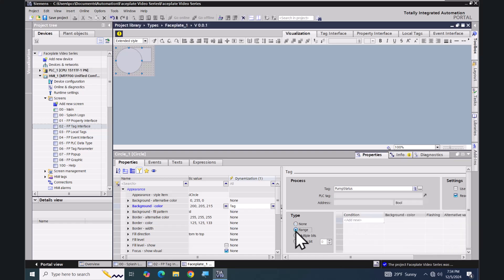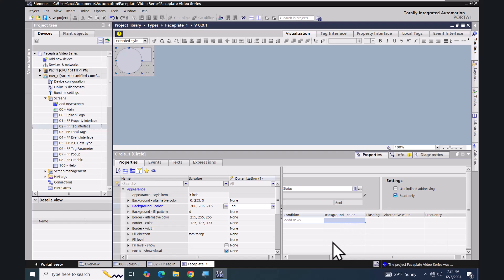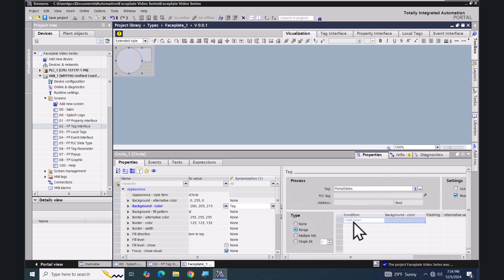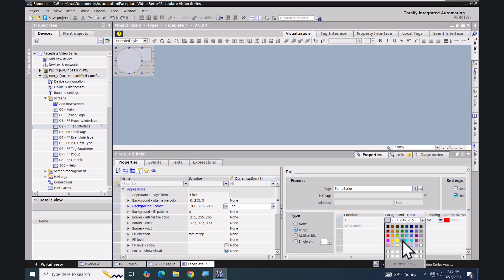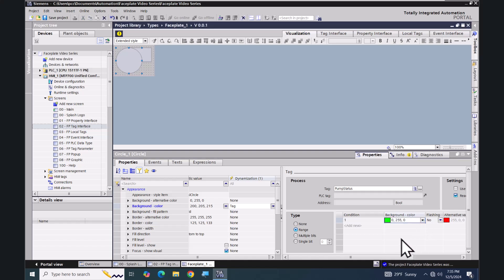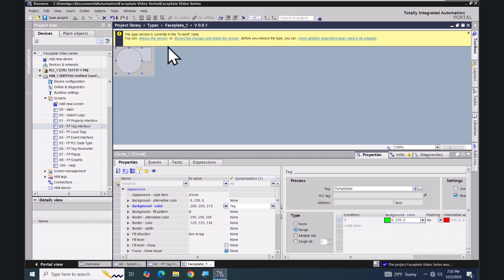I'm going to select 'Range' for the animation type and enter a condition of one, then select a background color of green. When you browse for tags inside the faceplate, you only have access to the faceplate tags created on the tag interface tab — you do not have the ability to browse for external tags.